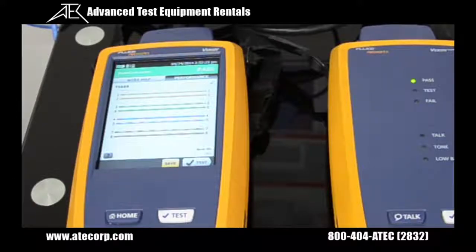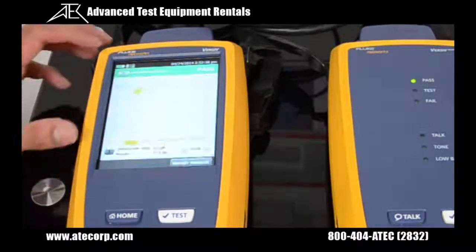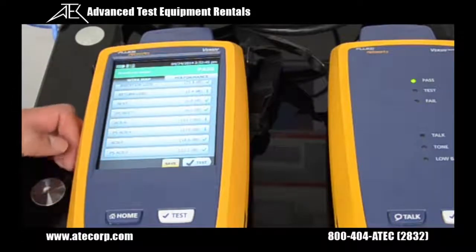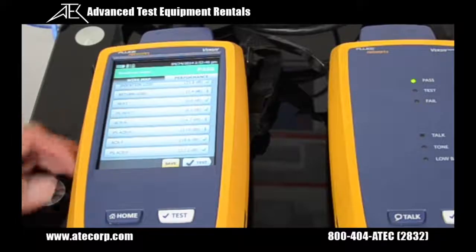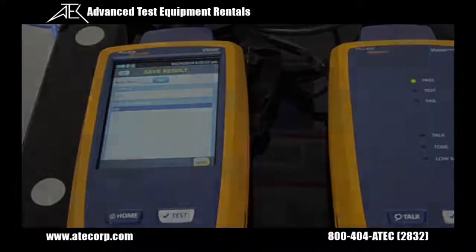My Versiv mainframe is telling me that the test passed, and it shows me the wire map. I could press the performance tab to see some of the actual test parameters, such as the length of the test, the resistance, the insertion loss, the return loss, the NEXT, the PS NEXT, the ACRN, the PS ACRN, and the ACRF. After I reviewed all these results, I could press the save button, and now I'm going to continue to my next test.